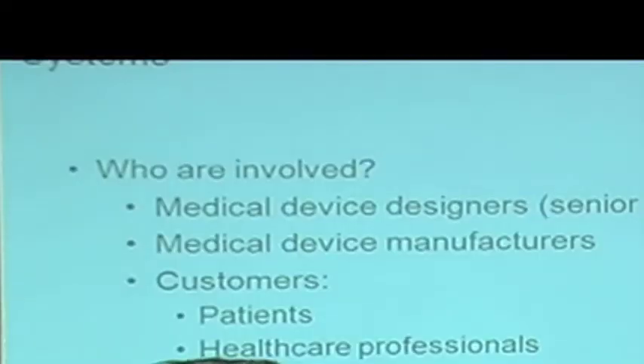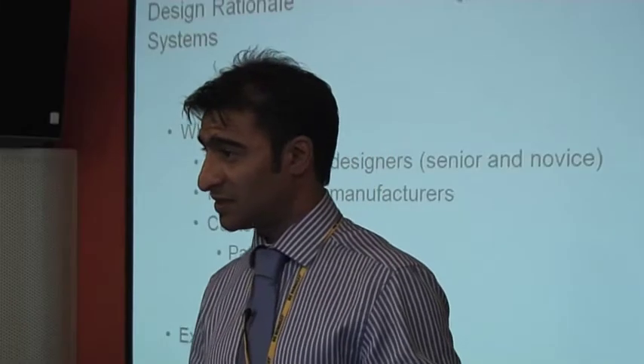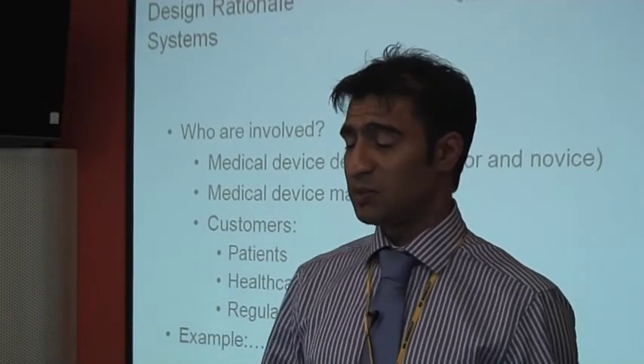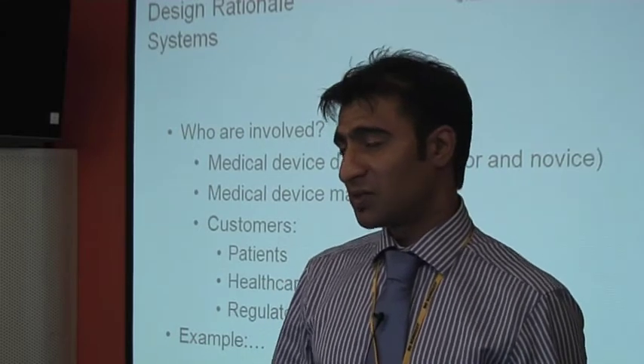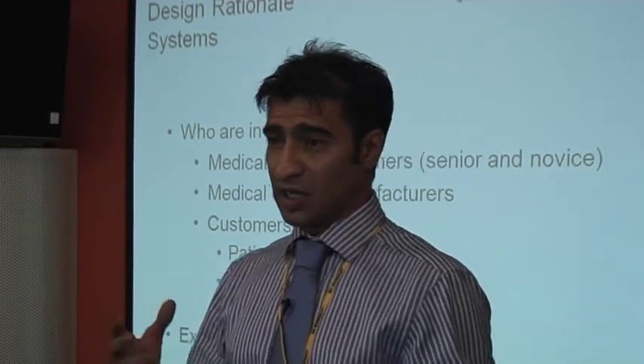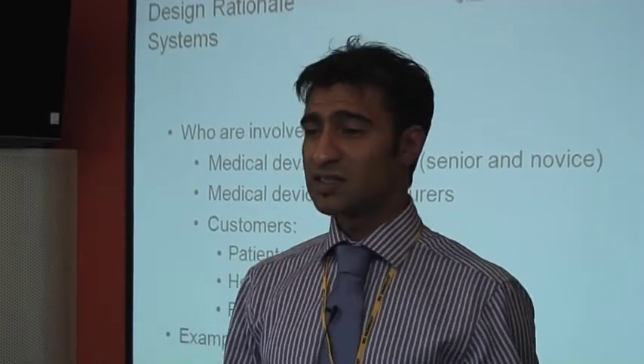So who are involved? Who are the actors involved in design rationale? They could be medical device designers — the people designing the devices — medical device manufacturers — the people making them — and the end customers, the people who use these. The regulatory authorities will also need to know how and why a device is developed the way it is, before it can be approved to market and before consumers can use that device.